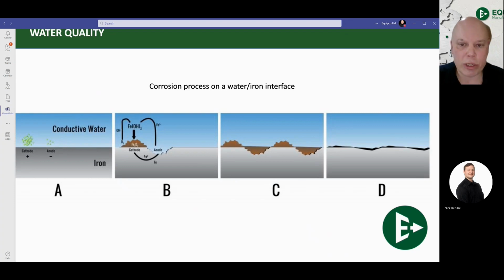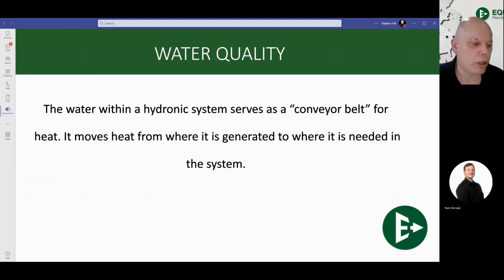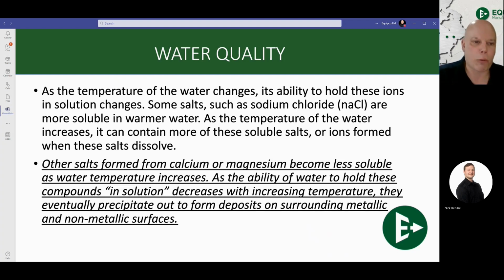So that's just number one stuff that is going to happen with regards to these ferrous materials, these other materials inside of water. So what I want you to think about is that water is like a conveyor belt. It's just designed to move that heat that you created in the heat exchanger, created in the boiler, and send it to that heat emitter where it's going to give off its heat, and then the water is going to come back to the boiler, get reheated. So it's a conveyor belt, just keeps on moving around and around and around.